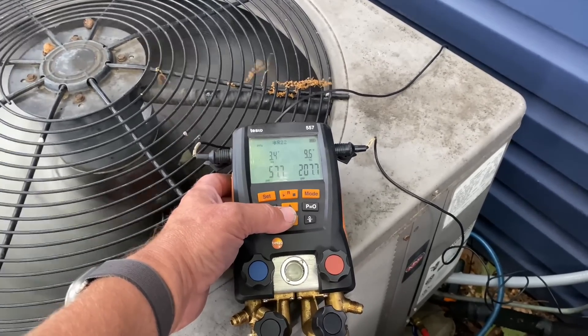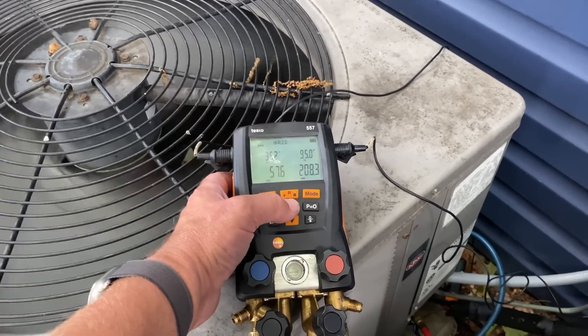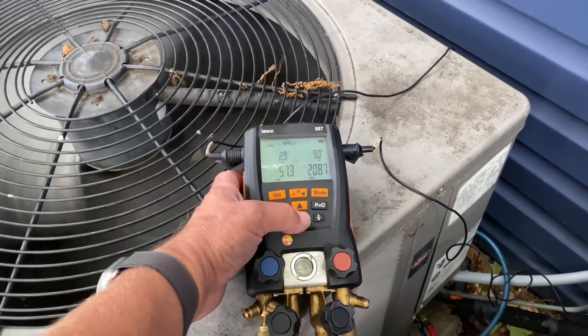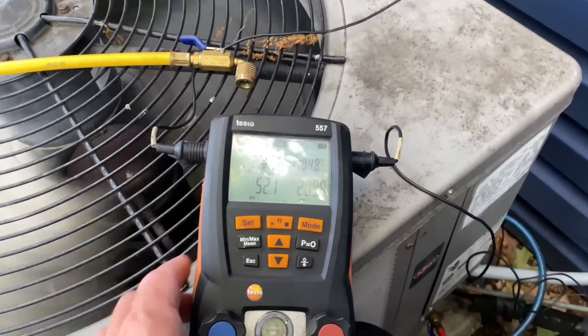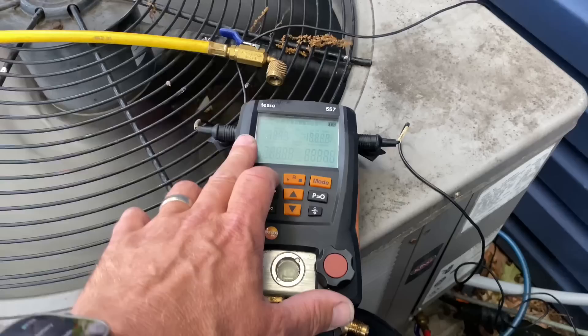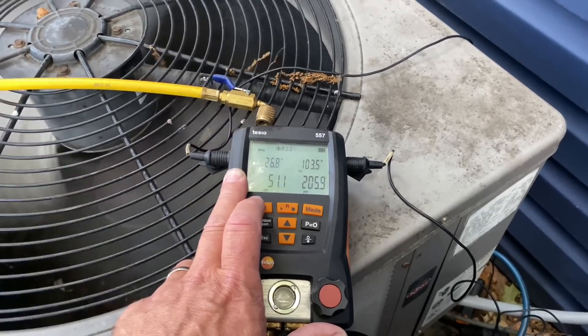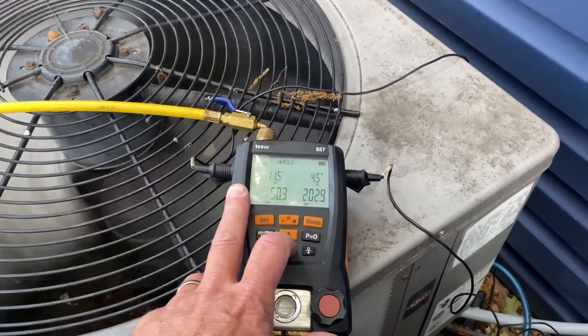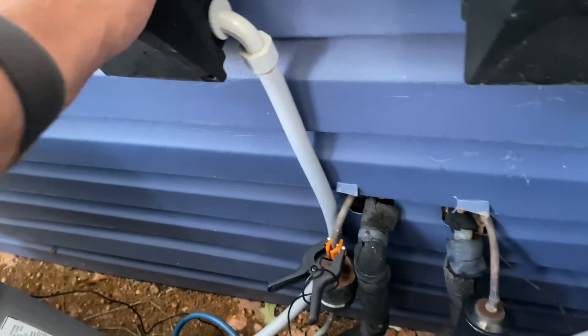Slowly dropping though — I would like to see this over 60 PSI, and I would like to see superheat. Only three degrees. Looks like we're undercharged. As we let the system sit a little bit longer, we're dropping down into dangerous territory on our suction side — we're at 51 PSI with an evaporator temperature of 26–27 degrees. Subcooling has now dropped to four and a half, and superheat has climbed to 11 and a half. We do have an undercharged condition here, which is indicative of a system leak.